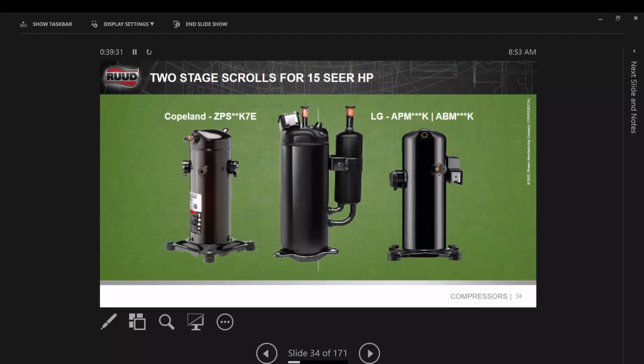So we have mainly three compressors that we're going to use in our system. Okay, the first one you're used to all the time is the Copeland K7. This is a typical two-stage compressor with an internal overload, just like you're used to using now. The middle is the Highly, that's the twin rotary. And then this one on this side is the LG, which is, if you open it up and look at it, almost identical to the scroll. It operates the same way as a scroll.